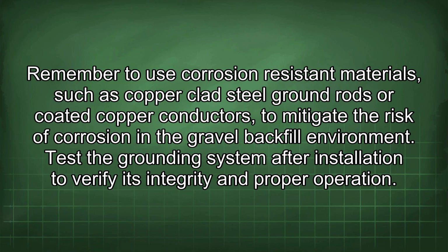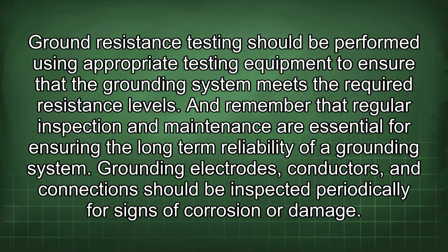Test the grounding system after installation to verify its integrity and proper operation. Ground resistance testing should be performed using appropriate testing equipment to ensure that the grounding system meets the required resistance levels. And remember that regular inspection and maintenance are essential for ensuring the long-term reliability of a grounding system. Grounding electrodes, conductors, and connections should be inspected periodically for signs of corrosion or damage.